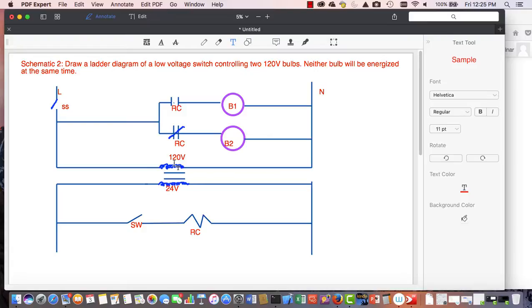So let's talk about sequence of operation. The service switch closes. My service switch is up here. Once it is closed, my transformer is getting 120 volts and generating 24 volts to my control circuit. Without closing SW, bulb 2 is on, because the normal position of this contact is closed, allowing power to flow. If I close switch SW, it energizes the relay coil RC, which opens the RC normally closed contact and closes the RC normally open contact. So when SW is closed and the coil becomes energized, it swaps which of these bulbs is getting power. Of course, nothing will happen if the service switch is open, because nothing is getting powered.